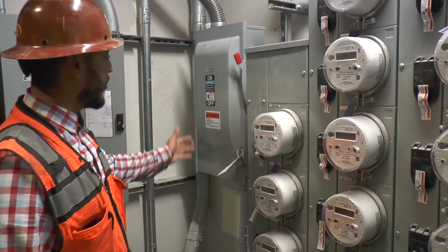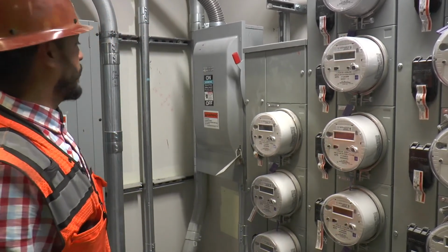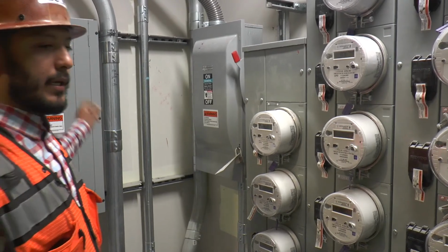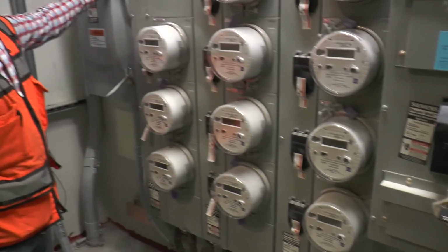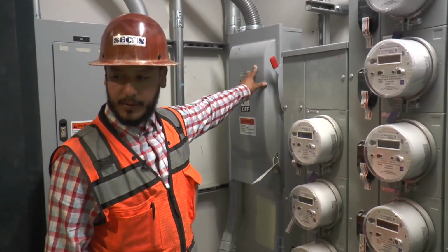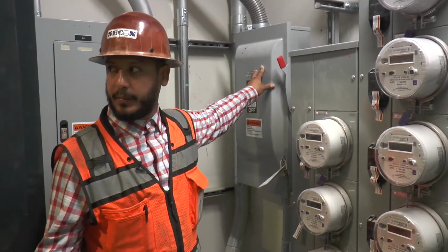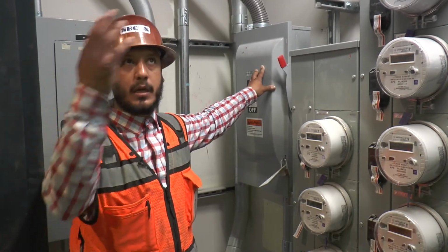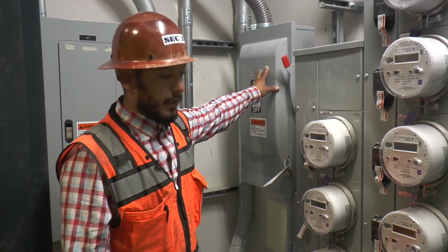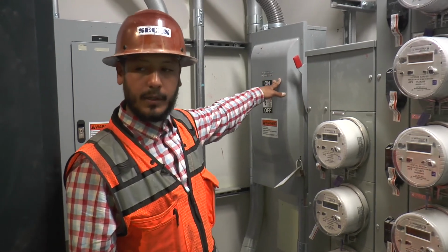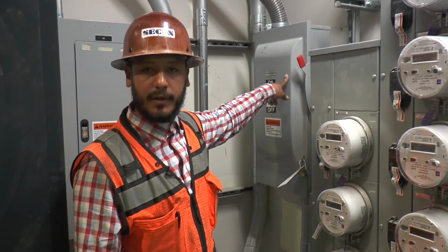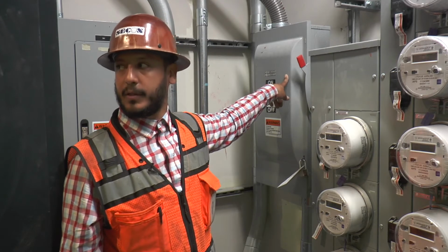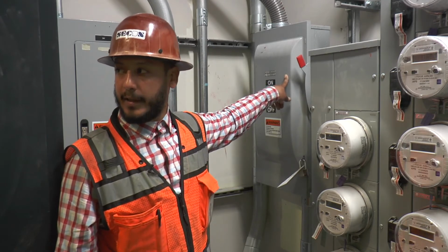Then over here we have our house power distribution. This is 9H1, where it first comes to, stepping down to the 75 kVA transformer to 120/208, coming to a disconnect to distribute to the low volt normal side panels for all your common areas, lighting and receptacles in these lobbies and corridors, exhaust fans. This will be feeding 13 L1, 16 L1, 19 L1, 22 L1, 25 L1, and 28 L1, and that's normal power.